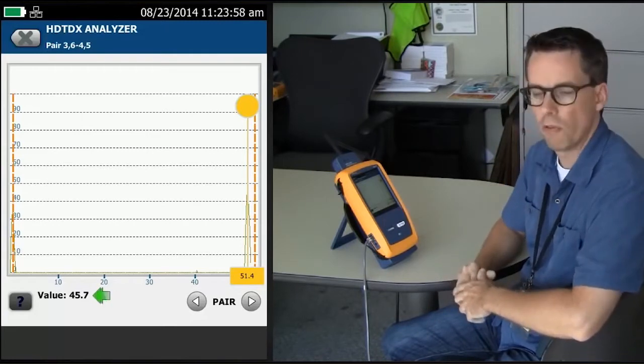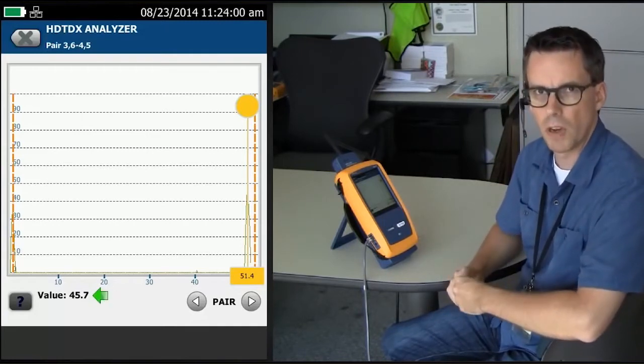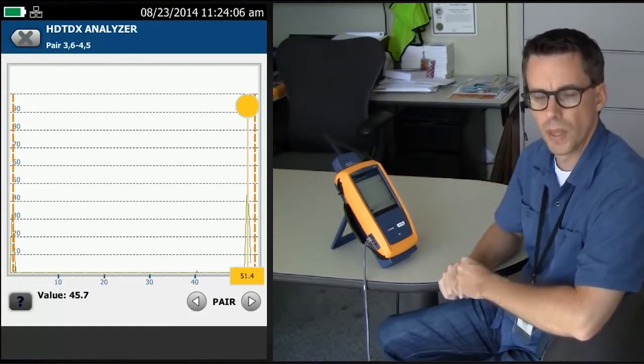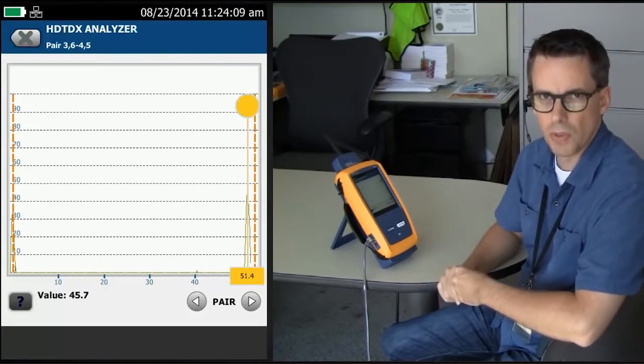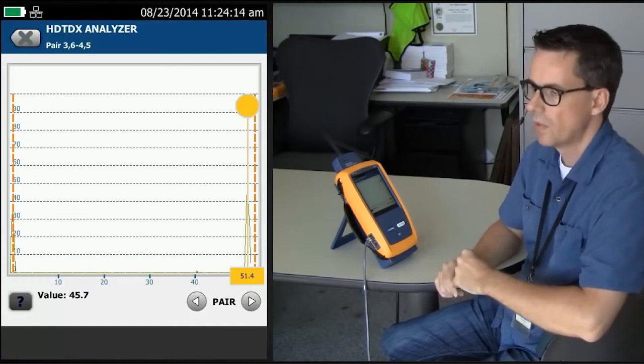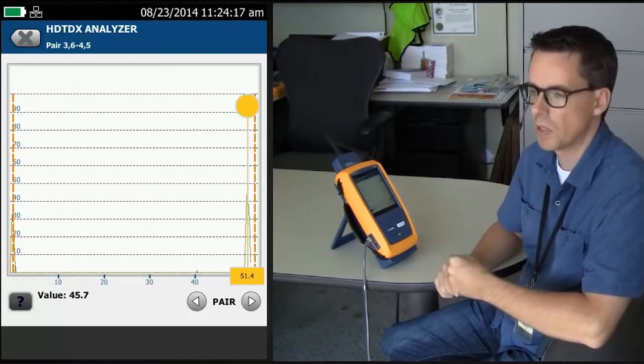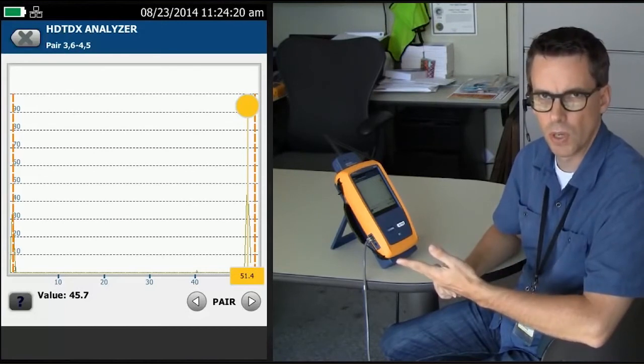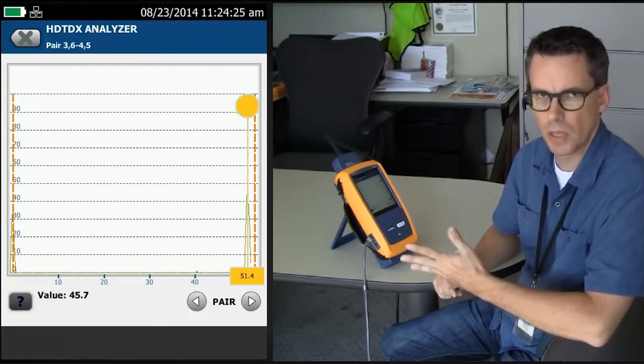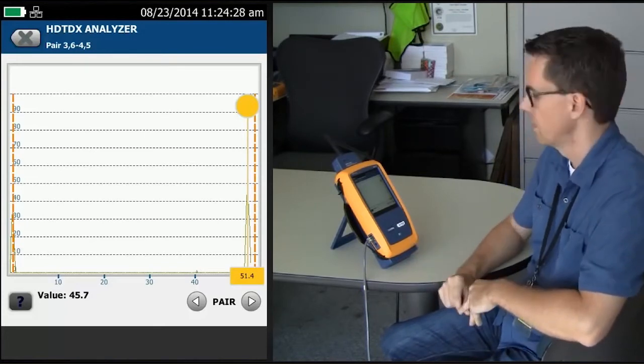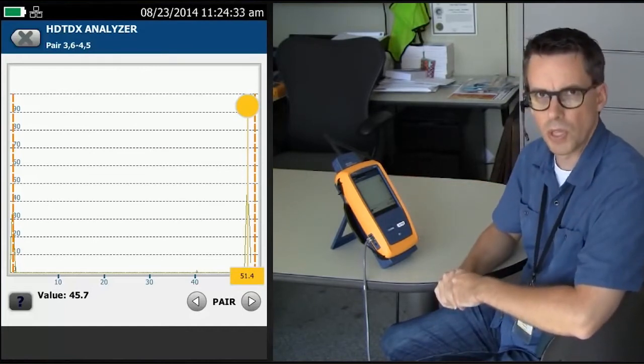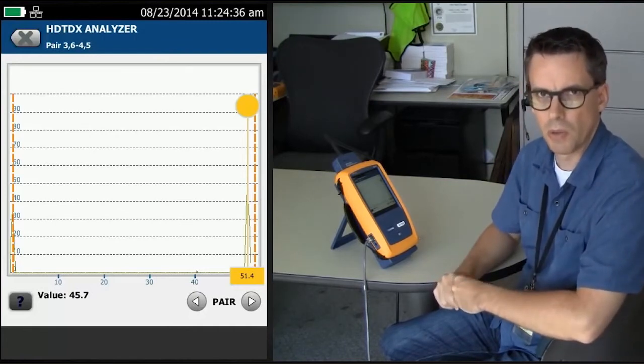Down here, we see a value of 45.7. That's 45.7 percent. That's relative to the vertical scale here. What does that mean? In an ideal world, we're looking for better than 30 percent where the connections are. 30 to 35 is ho-hum. 35 to 40, you should start getting nervous because you're going to start seeing reduction in margin on your near-end crosstalk test. And generally, anything over 40 suggests that something didn't quite go right during that installation. When we look at this one here, the far end connection is reporting 45.7. That's simply too much crosstalk going on in that remote connection.